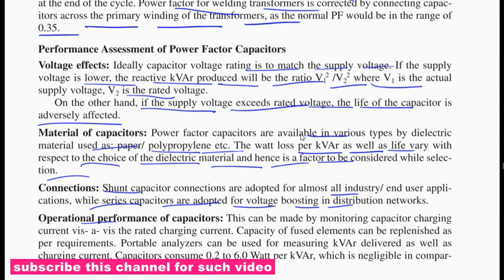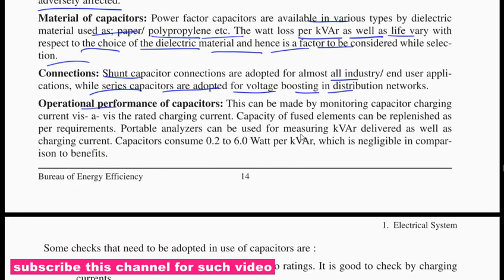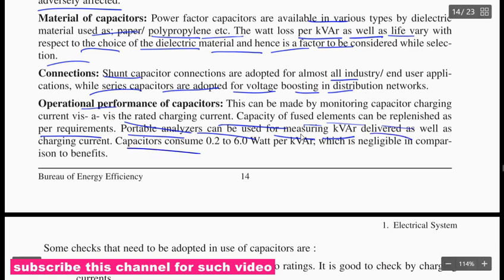Operational performance of capacitor. This can be assessed by monitoring the capacitor charging current against the rated charging current. The capacity of the fused element can be replenished as required. A portable analyzer can be used to measure kVAr delivered as well as charging current. The capacitors consume 0.2 to 6.0 watt per kVAr, which is negligible overall.